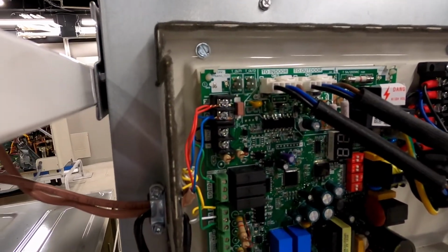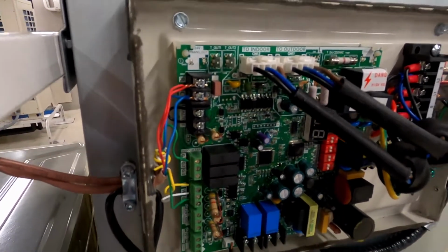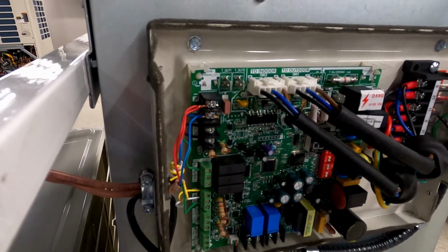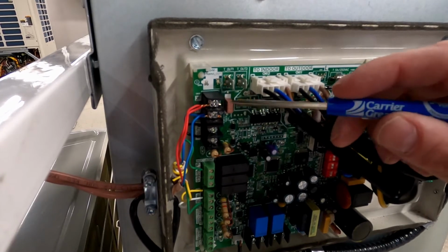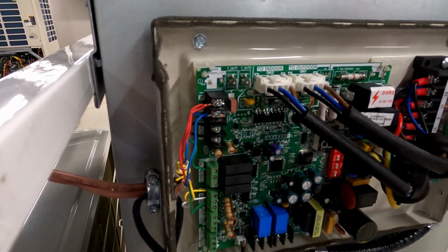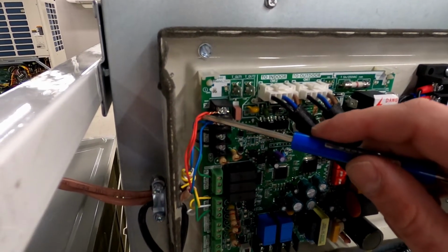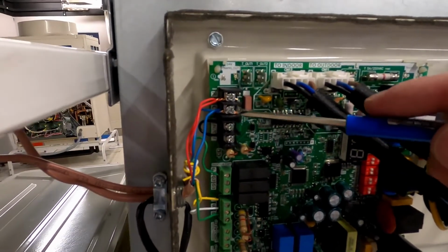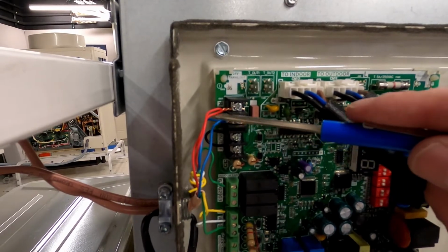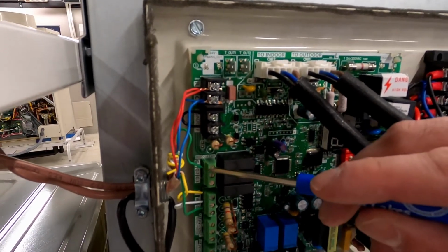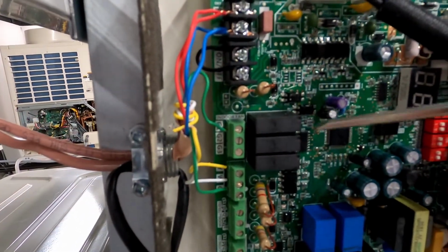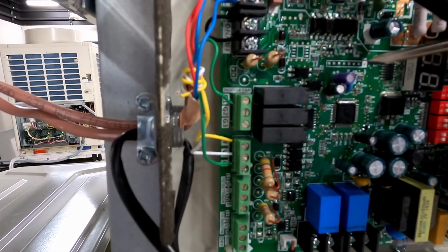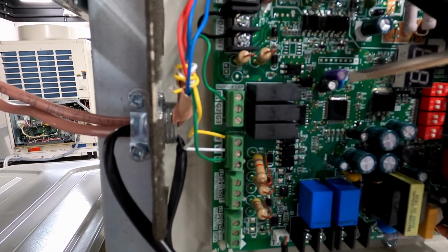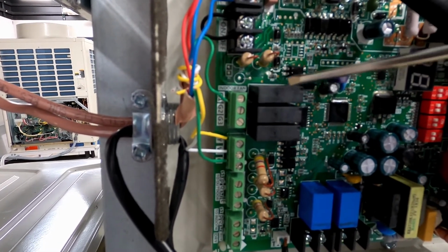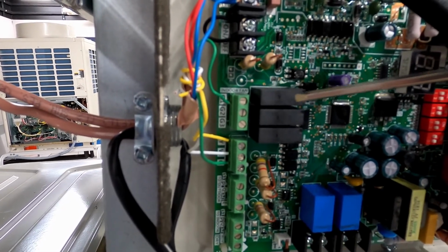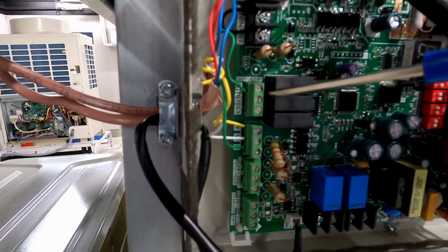Now we're going to hook up our low voltage control wiring. So we have two sets of thermostat wires. I'd recommend using a 6 or 8 wire so that you have extra. We're getting our 24 volt power to the interface kit and to our thermostat from the transformer in the air handler. So we have both of the R wires and both of the common wires tied together underneath these terminals. One set comes from the air handler and the other set goes to the thermostat. Then we also have our G1, which goes to the air handler. So the interface kit controls the fan operation in heating, cooling, and when the thermostat gives a call for fan. So G1 will be energized on a call for heating, cooling, and it will de-energize in defrost mode. So we hook our G wire from the air handler to G1.